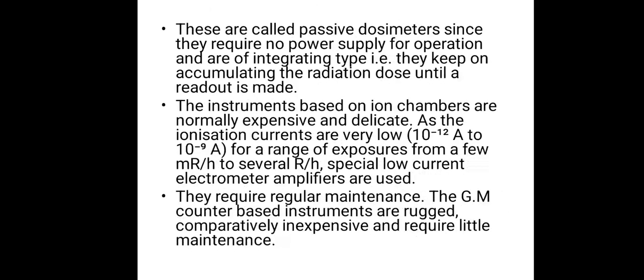These are called passive dosimeters since they require no power supply for operation and are of the integration type. For example, they keep on accumulating the radiation dose until a readout is made.